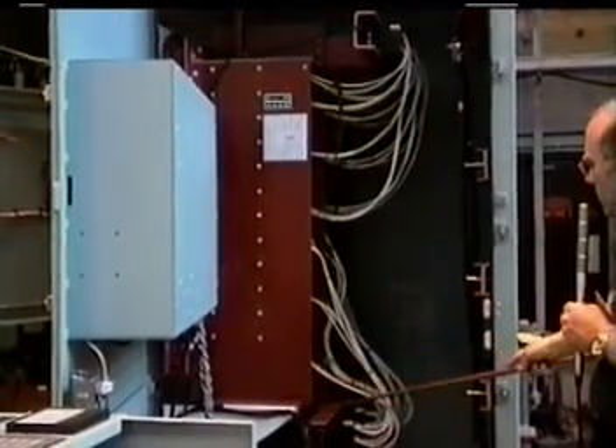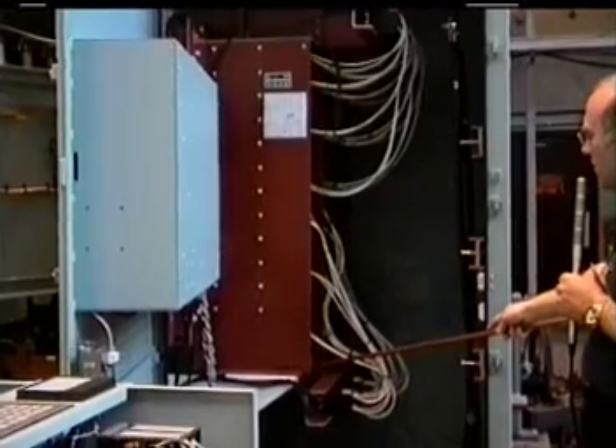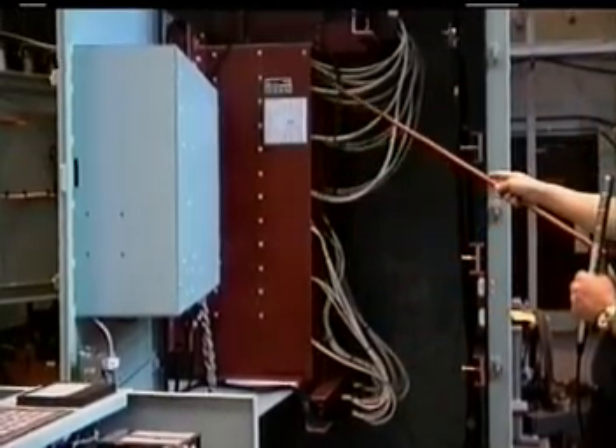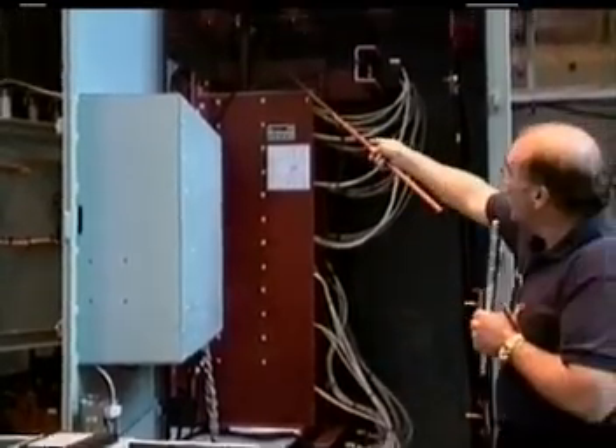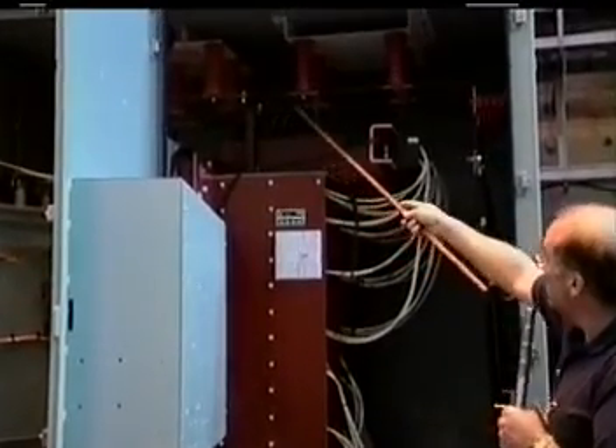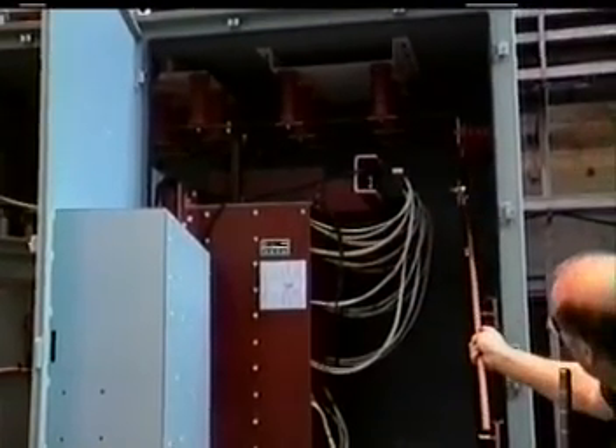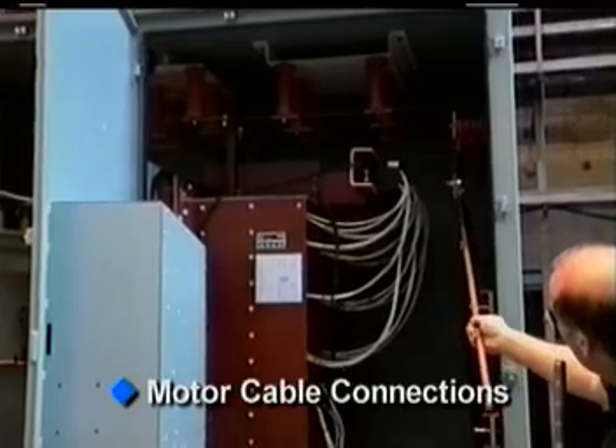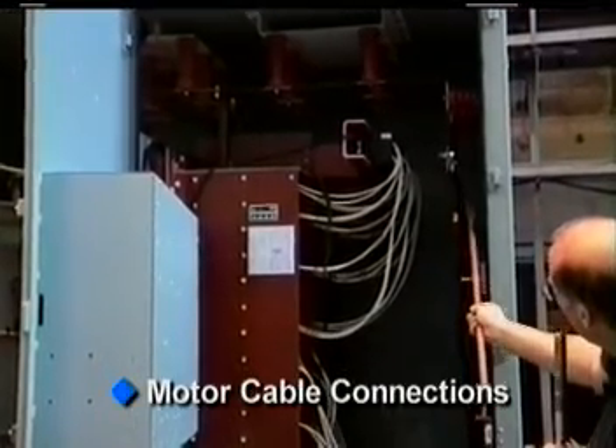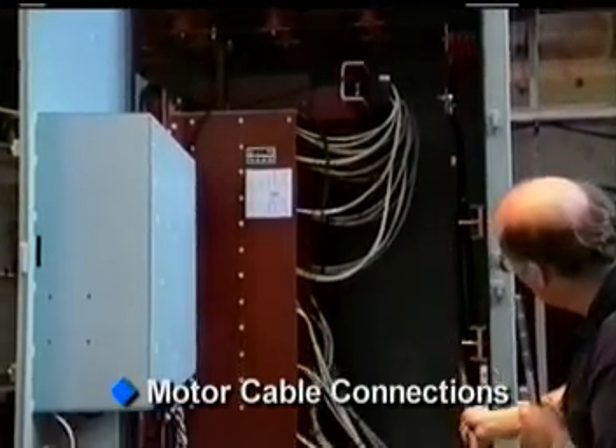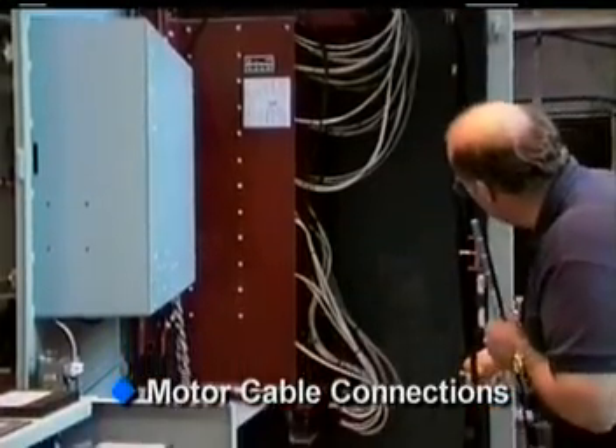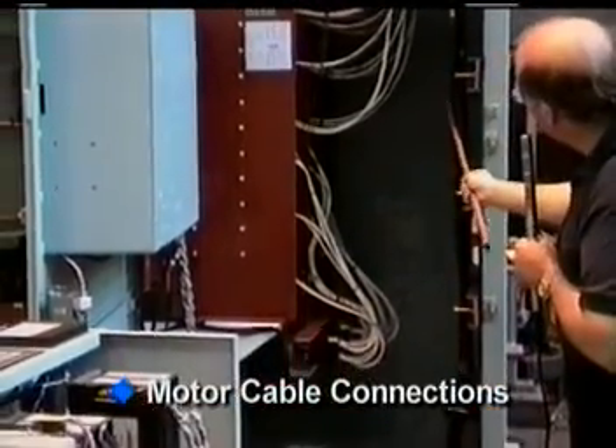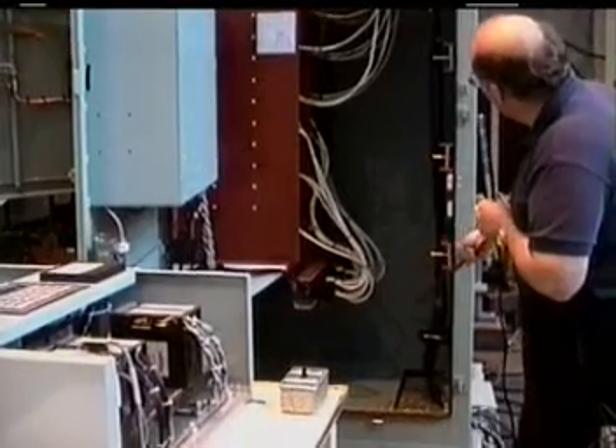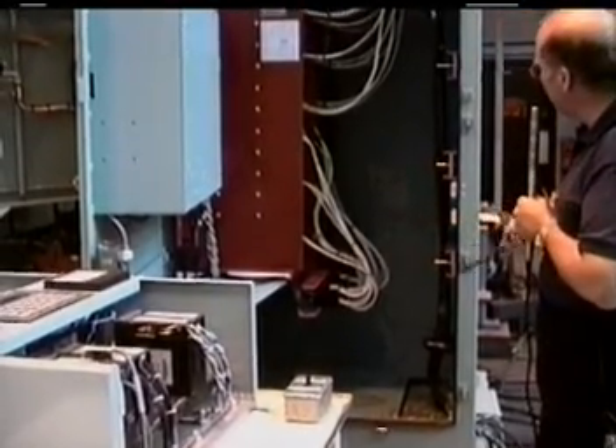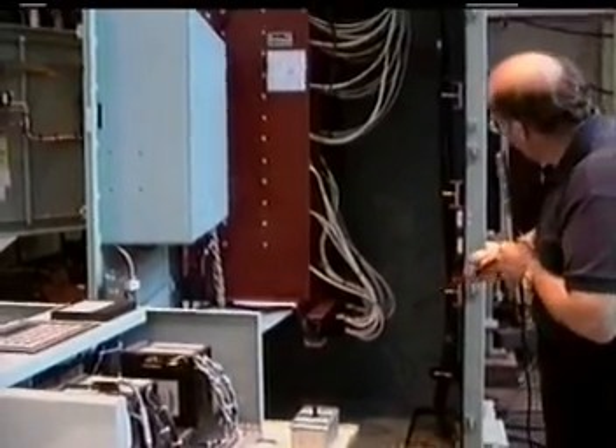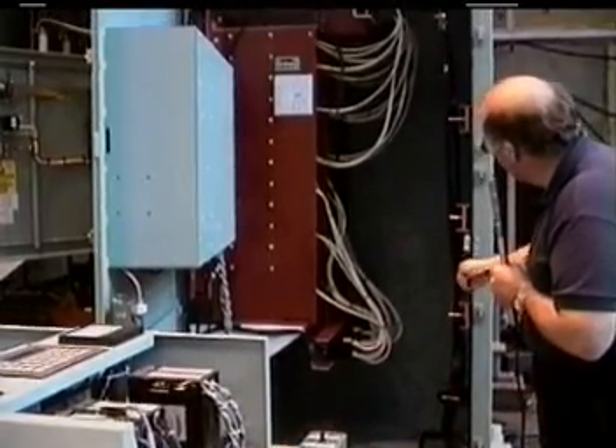The bottom section over here is where we bring input power, and then output power flows up through here to the output of the stacks, which then comes over to here and forms the T connections where the customer can bolt on his motor connections here. And there's bracing provided on the sidewall of the enclosures to provide for mechanical protection so that the wires don't move during operation from mechanical forces caused by the current within the conductors.